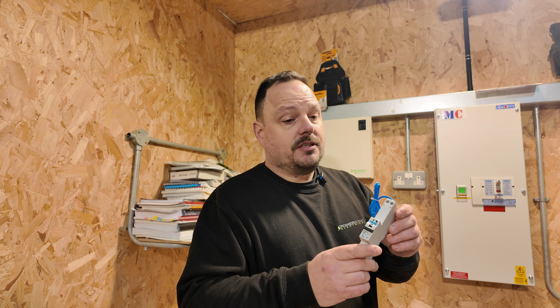So there are those options off the shelf, and obviously this is going up to the 100s of amps, and you can scale it as well from 30 milliamps all the way up to the 1.5 amp range. And as we discussed in the video, those are all adjustable and settable depending on the size of your MCCB. And there are applications where you're going to have selectivity in your RCD protection. I know from speaking with Neil Bridgman and the challenges he faces in the railway sector, for example, where your source RCD protection might have to be one or several amps rather than 30 milliamp rated due to selectivity as you move through those circuits. And these are a great way of achieving that.